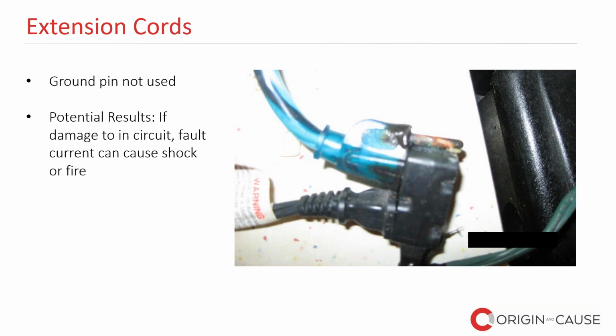So in this situation, in terms of grounding, what is the ground pin's purpose? Grounding any electrical equipment provides a path in case an electrical fault arises that's trying to find a path to the ground and back to the source. If you have no path, this electrical current could take any other conductive surface as its path, and it could create a shock and in some cases a fire hazard. So the potential for damage in the circuit on the cord could possibly cause a fire.